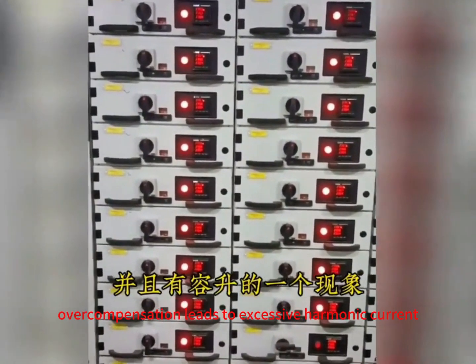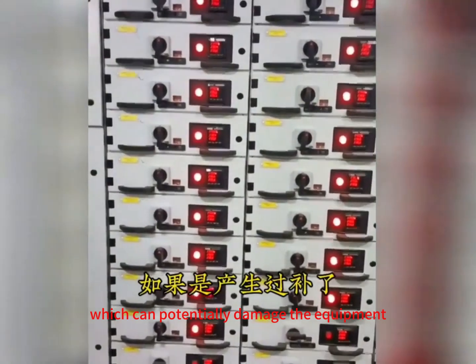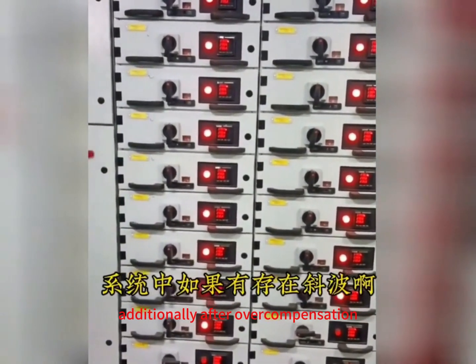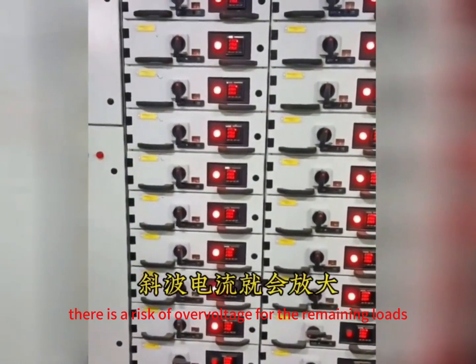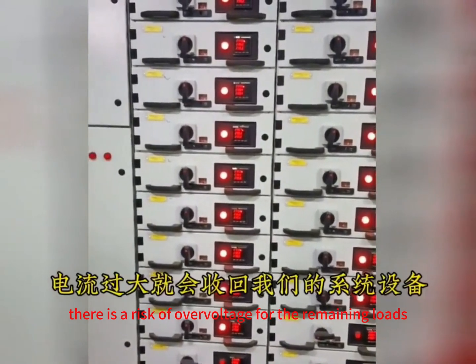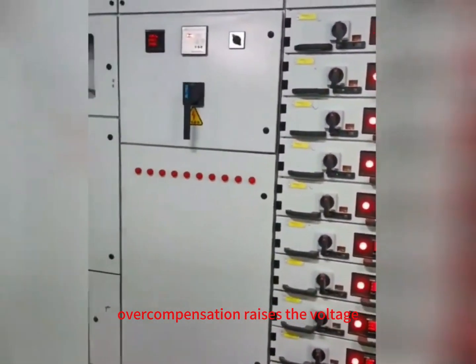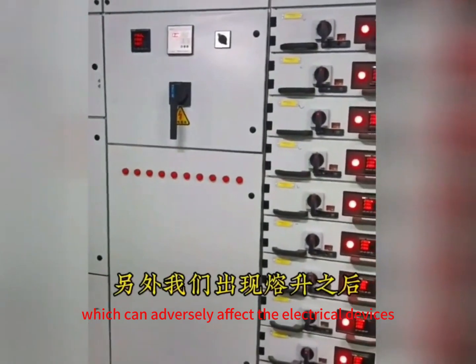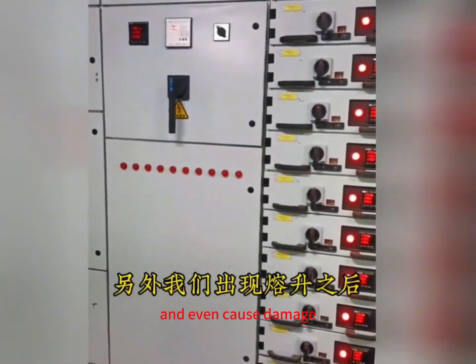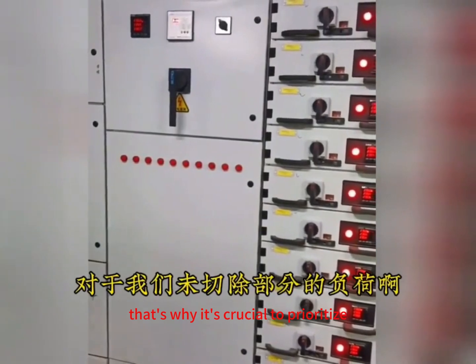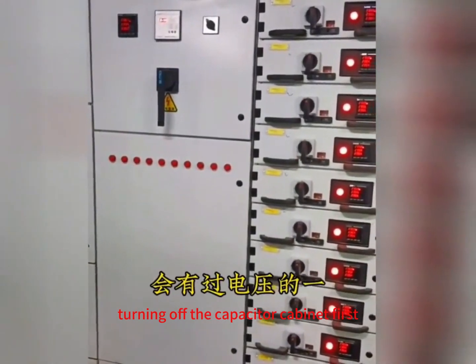Overcompensation leads to excessive harmonic current, which can potentially damage the equipment. Additionally, after overcompensation, there's a risk of overvoltage for the remaining loads. Overcompensation raises the voltage, which can adversely affect the electrical devices and even cause damage. That's why it's crucial to prioritize turning off the capacitor cabinet first during power off.